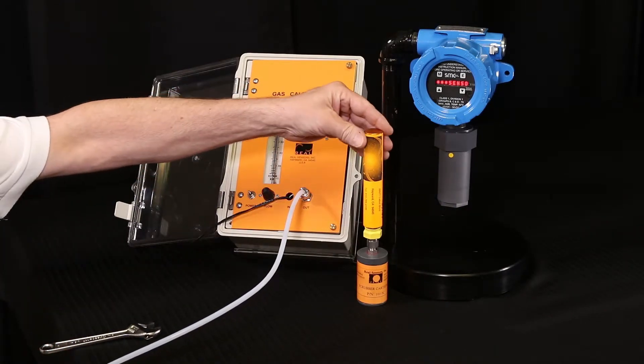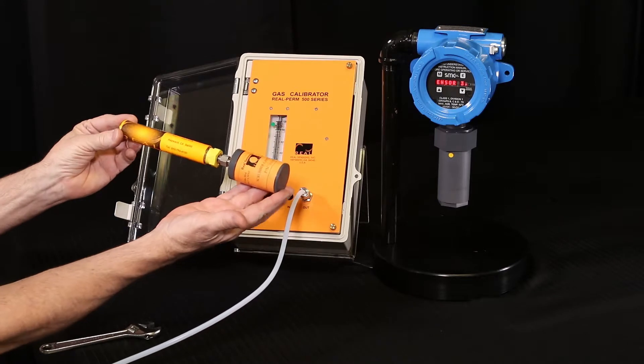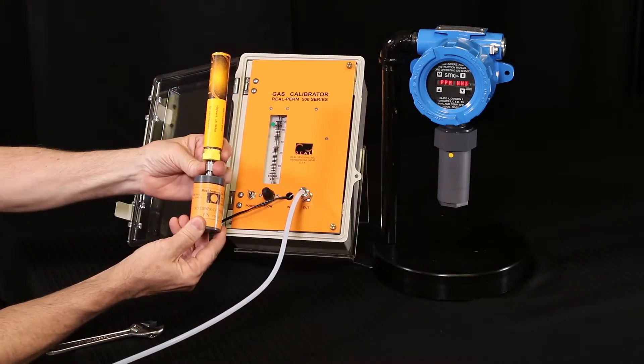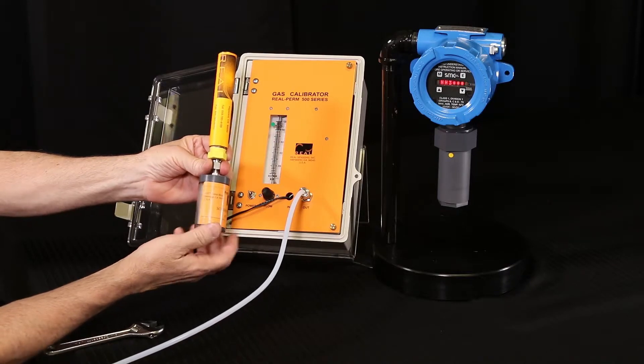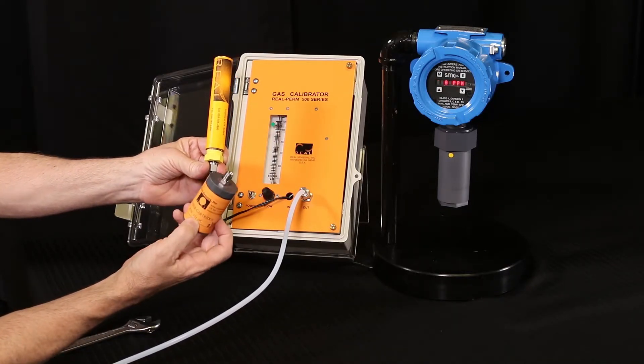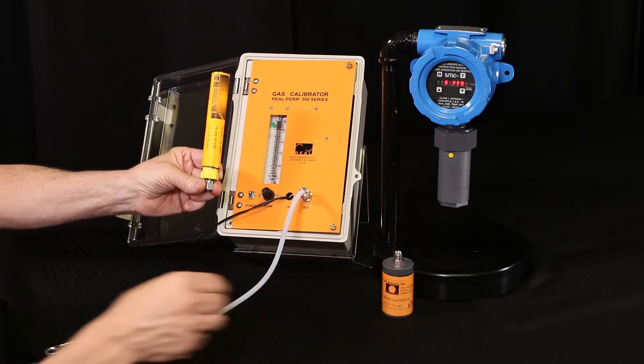Please verify that the permeation tube is not expired. If expired, replace immediately. The permeation tube is shipped with a scrubber cap that must be replaced when the tube is not in use. The tube must also be removed from the calibrator when not in use to prevent contamination of internal components.